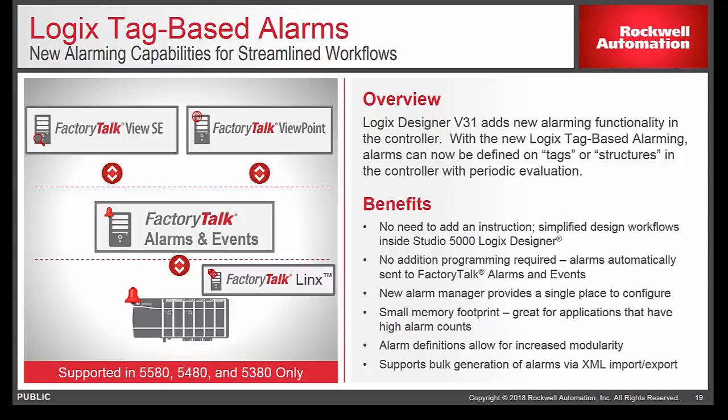Logix-based alarms were created and managed in the Logix Designer environment with 2 specific instructions: ALMA for analog alarms and ALMD for digital alarms. Those instructions would be added specific to the program code to implement Logix-based alarms in your Logix engine.